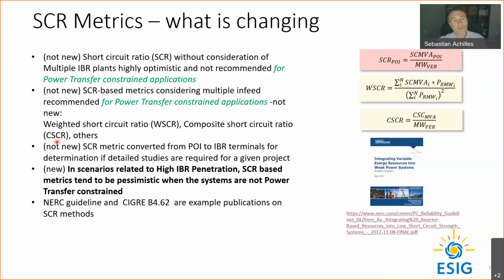There are a number of steps that are done. If a transmission company or reliability entity calculates a short circuit ratio at the point of interconnection or a high level, there's a translation of that short circuit ratio to the terminals of an inverter-based resource. Then the manufacturer may provide guidance on to what extent that level of short circuit ratio was incorporated into the design, and whether there are risks or not. Based on that, there could be decisions about doing detailed studies.